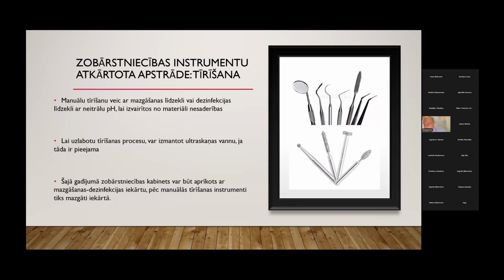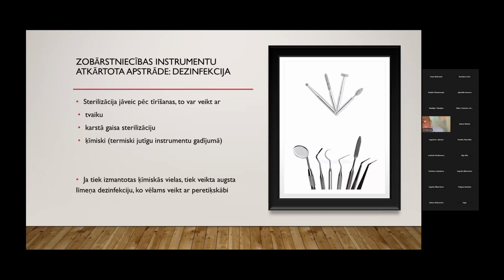Ultrasonic baths also are quite popular in the dental environment. And also dental offices can sometimes be equipped with a washer disinfector. So in this case, you need to use the proper product for such a device. The sterilization has to be made after the cleaning, of course. It could be made with steam, with dry heat sterilization, or it could be chemical in terms of thermosensitive instruments.